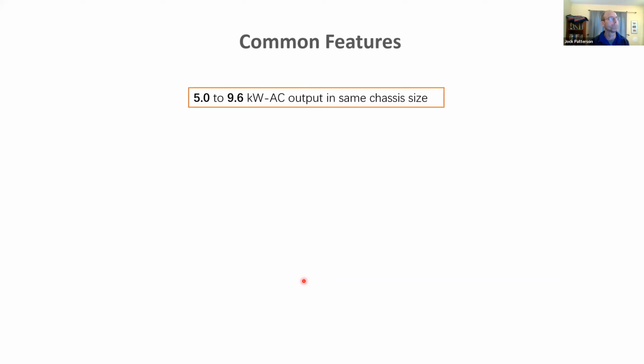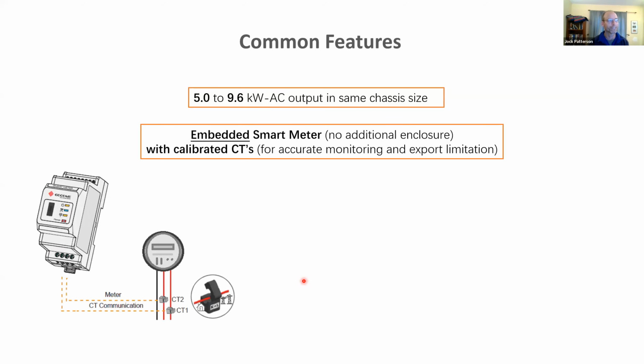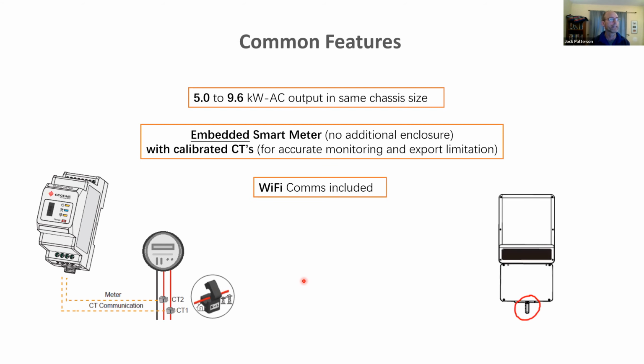So across those 3, there are 6 power classes from 5 to 9.6, with the common classes being 5, 7.6, and 9.6. Included inside the inverter, already wired, so there's no need for an external box, is a smart meter. Inside the packaging for the inverter is also a set of CTs, so you can install those. For the PV inverter, it's not required. It is recommended. I'll explain that in another slide. And again, across all 3, you can choose to use the included Wi-Fi communication module, which we call a Wi-Fi dongle. It plugs in the bottom, and it's represented in the bottom right in the red circle. It's the last thing you'll do after installation, but right before you start commissioning. Other forms of communication would be a cellular or LAN connection.